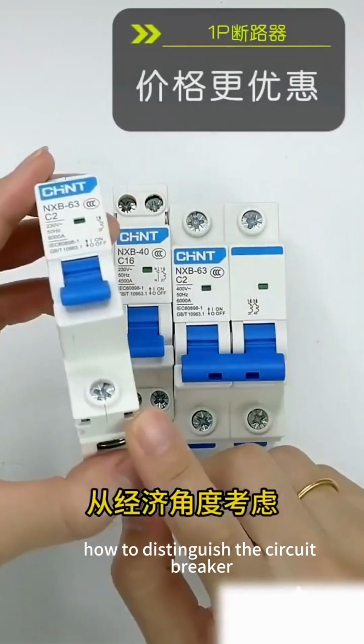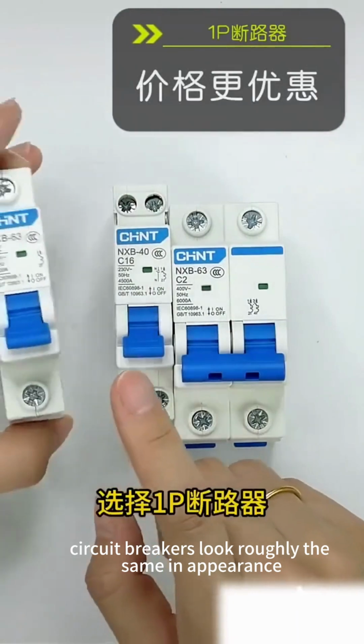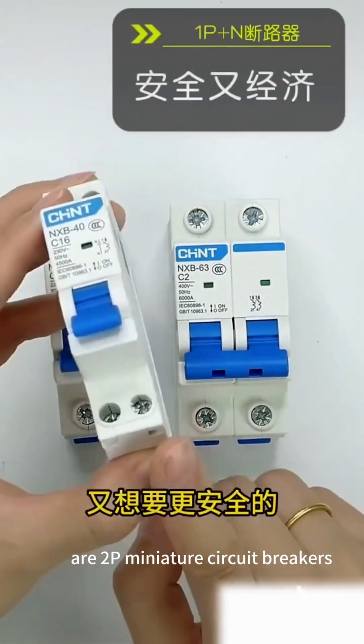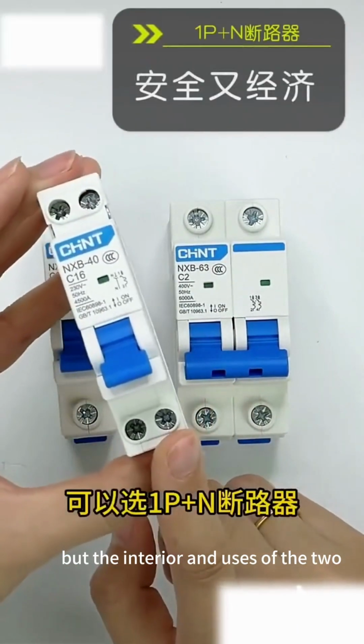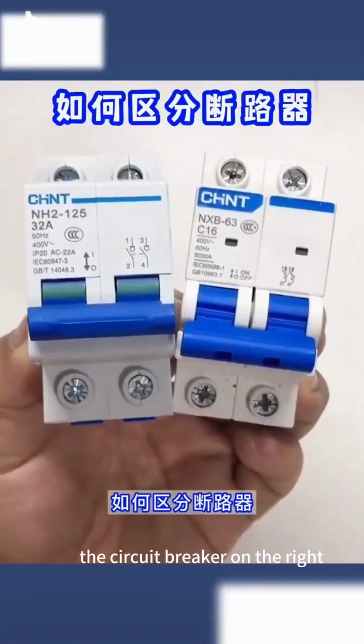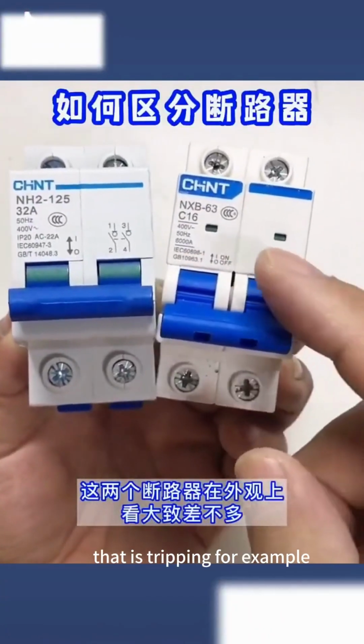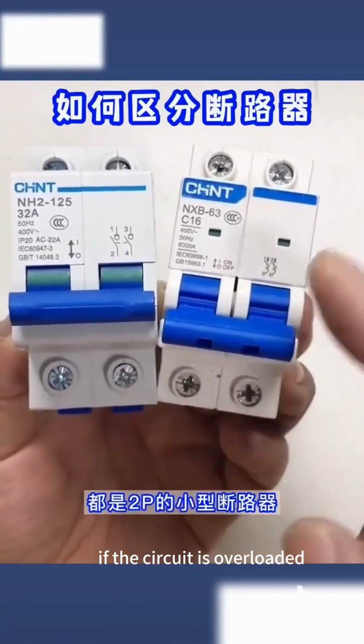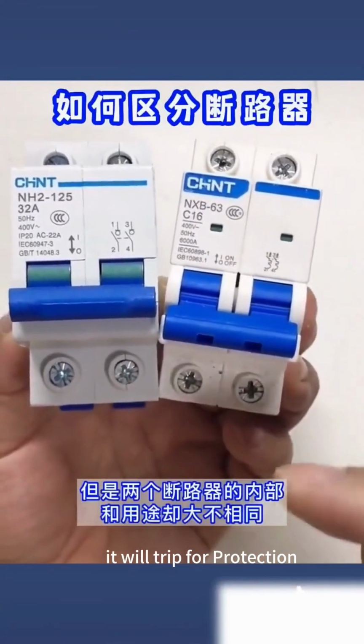How to distinguish the circuit breakers. These two circuit breakers look roughly the same in appearance, and are both 2P miniature circuit breakers, but the interiors and uses of the two are quite different. The circuit breaker on the right has the function of automatic tripping. For example, if the circuit is overloaded or short-circuited, it will trip for protection.